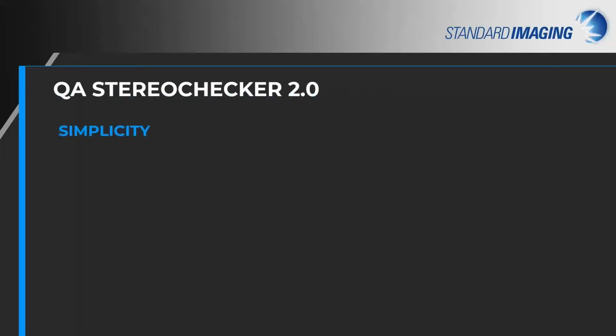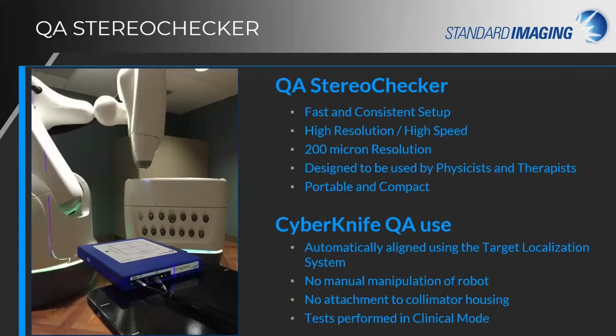StereoChecker 2.0. Simplicity, workflow, results, reimagined. The QA StereoChecker is a high-resolution, portable, amorphous silicon detector for machine QA. While originally designed specifically for CyberKnife QA to provide a fast and filmless means to perform machine QA, it may also be used on other Linac systems to provide quick analysis of single-field images.